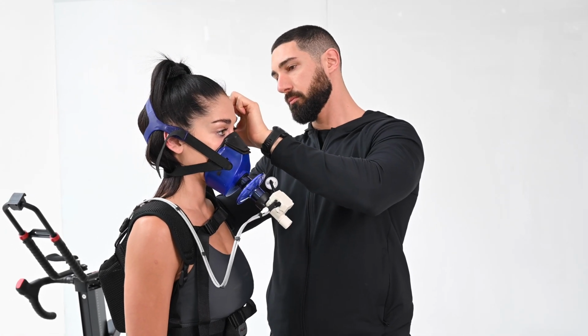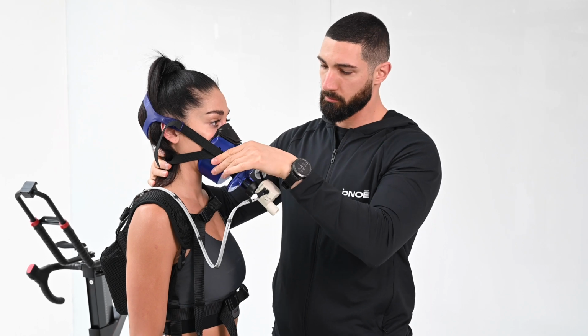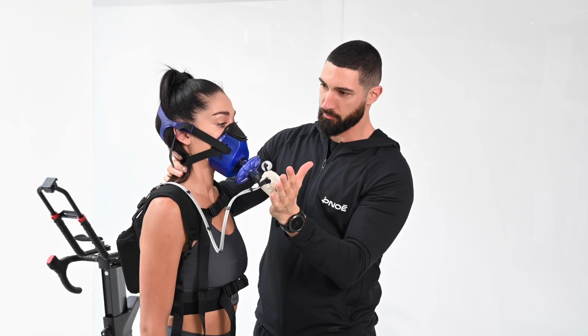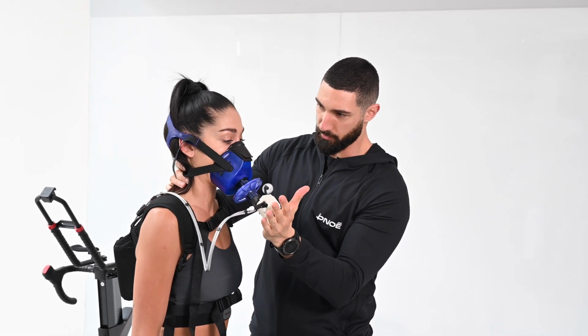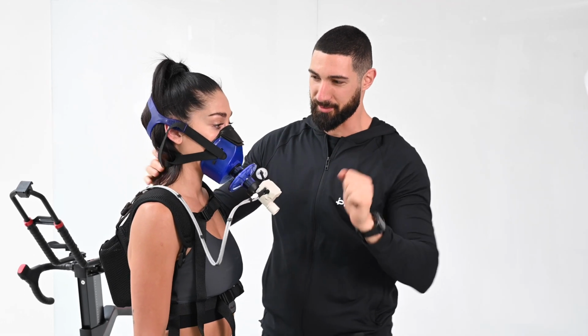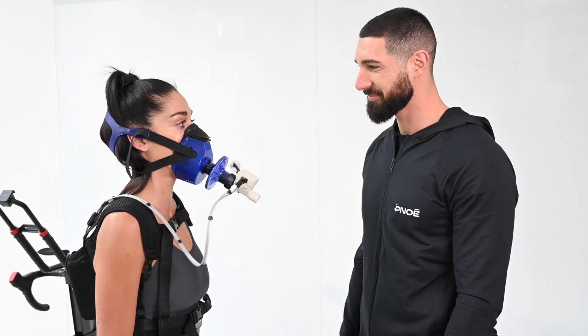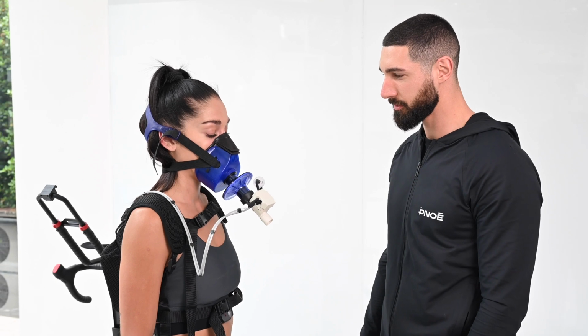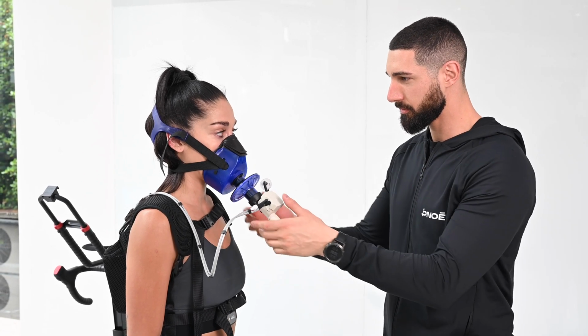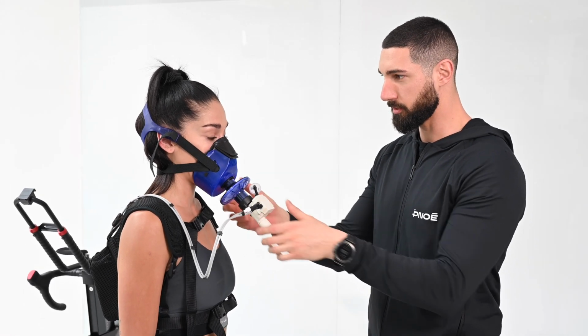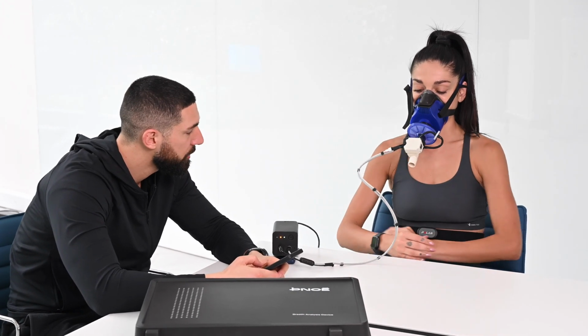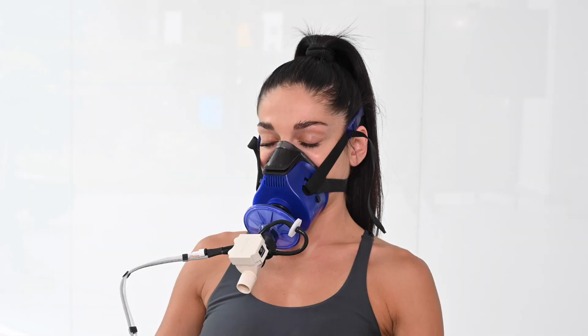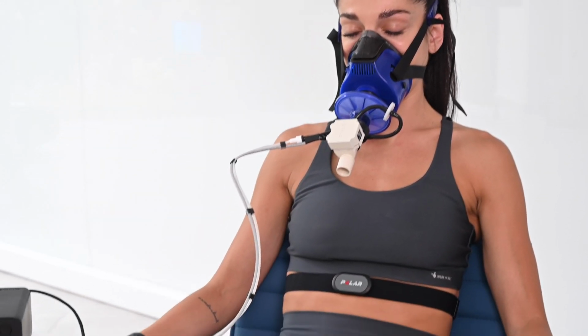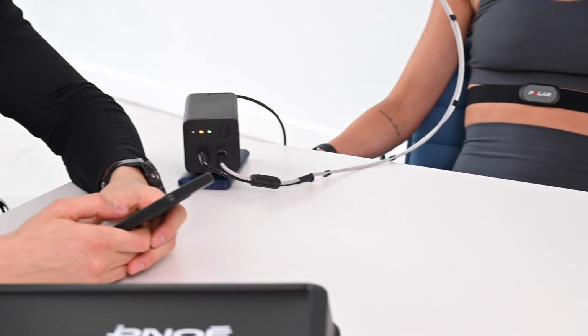Since the mask has been fitted, it is time to perform a seal check to see if there are any leakages coming from the mask. In order to do this, block the flow sensor with the palm of the hand, and ask the subject to steadily exhale to see if they feel any leakages. If no leakages are felt, you are all set to proceed with the measurement. If you are performing an RMR test though, it is not necessary for the testing subject to be wearing the backpack and it can be placed beside them.